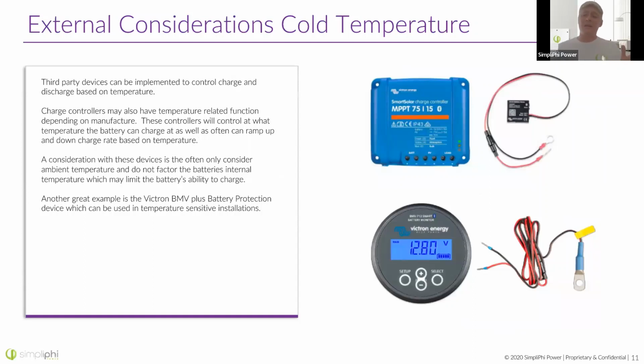Now, there is even another way you can mitigate cold temperatures by simply preventing charging from an external device entirely. So if you don't have SimpliPhi communications with a compatible inverter charger, another thing you can do if you're using Phi batteries is just use a Victron charge controller with a temperature sensor in tandem. The temperature sensor will attach directly to the battery terminals and tell the charge controller an accurate temperature for the outside of the battery case.